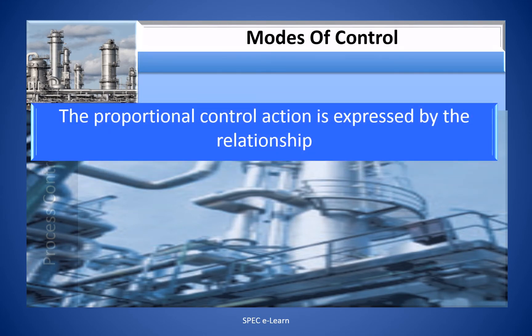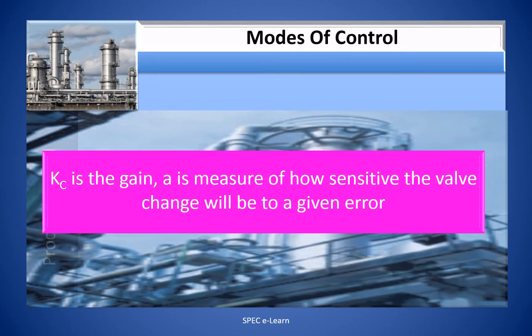The proportional control action is expressed by the relationship: MV = KC·E + I, where MV is the manipulated variable, KC is the controller gain (which is adjustable), E is the error, and I is the initial value of MV — the controller output or offset. KC is the gain, which is a measure of how sensitive the valve change will be to a given error.